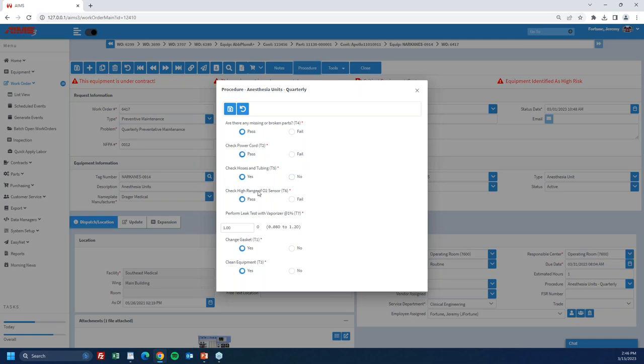Did you check the hoses and tubing? Yes. Did you check the O2 sensor? Yes. Okay, tell me what the leakage test for that vaporizer was. What's the plus or minus? It needs to be within this range.